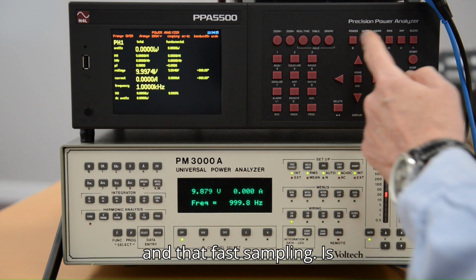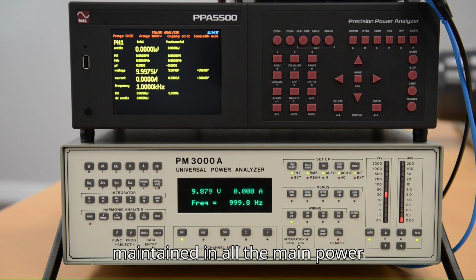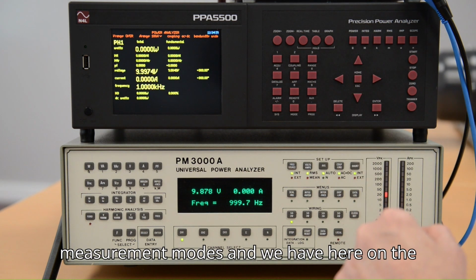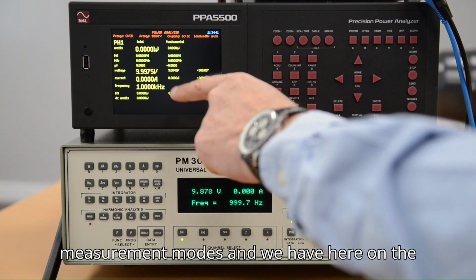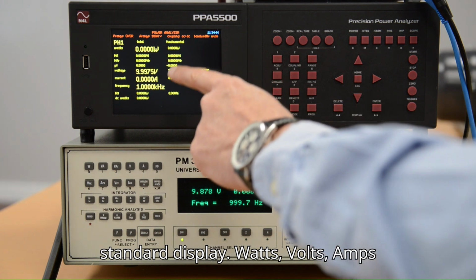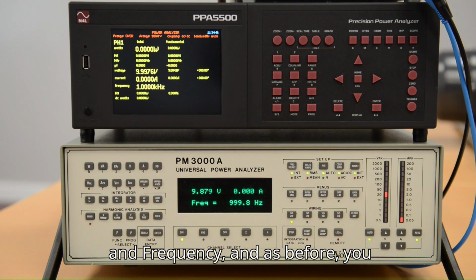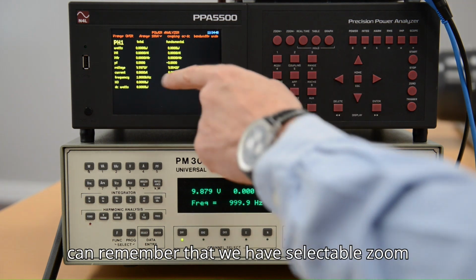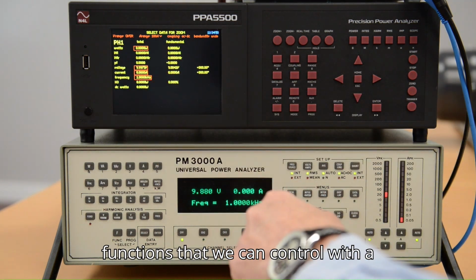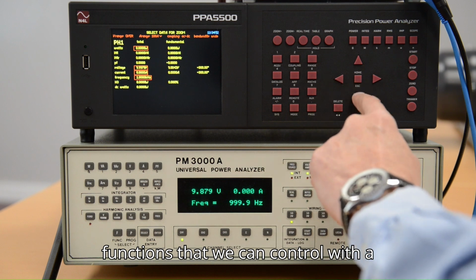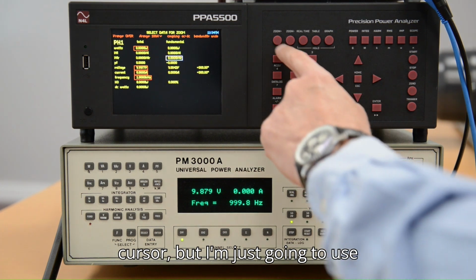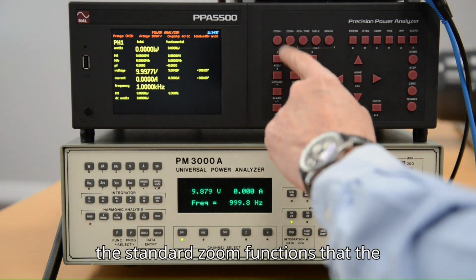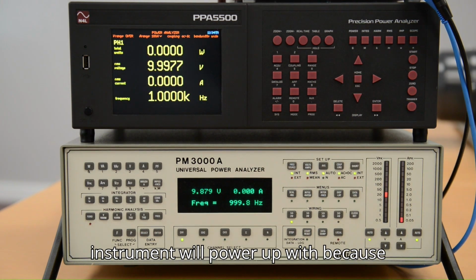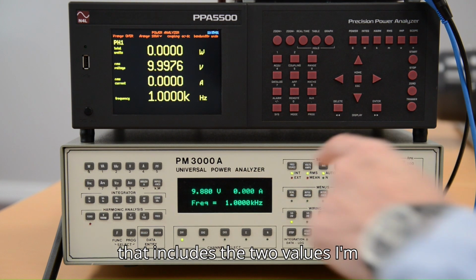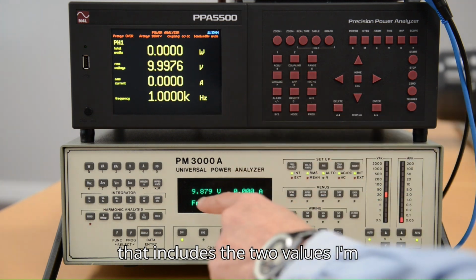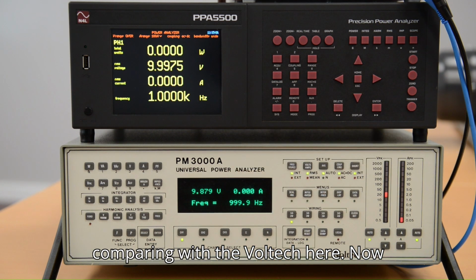And that fast sampling is maintained in all the main power measurement modes, and we have here on the standard display watts, volts, amps and frequency. And as before, you can remember that we have selectable zoom functions that we can control with a cursor, but I'm just going to use the standard zoom functions that the instrument will power up with, because that includes the two values I'm comparing with the Voltech here.